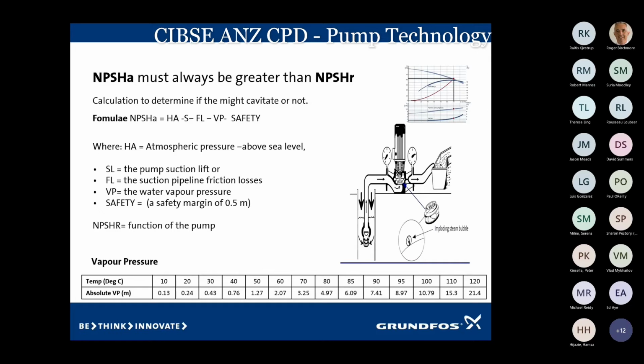One thing to be aware of is always consider if at some stage that pump may shift along the curve, because if that pump moved from 70 cubes to 80 cubes, then your net positive suction head requirement has just shifted up to just over 4 meters, and that could be the difference. You could then have a greater net positive suction head required than your net positive suction head available, and then the pump just won't work.